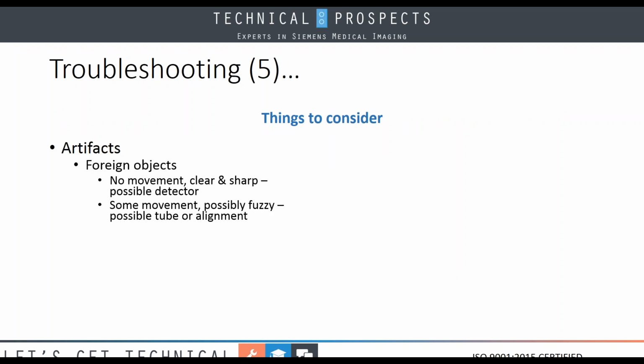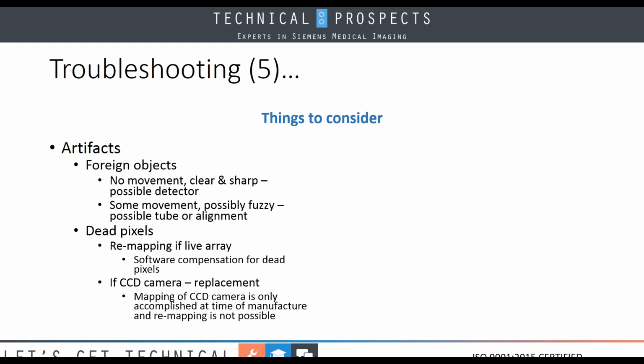When we look at artifacts here, foreign objects, all right, if they don't move and they're clear as sharp, it's possibly right on the detector. If they move around on different images, maybe a little fuzzy, maybe it's the tube or an alignment issue. When we look at dead pixel artifacts, all right, remap if it's a live array. The reason that remapping is important is because if the software knows a pixel is bad, it will then look at the 8 surrounding pixels and compensate for that known bad pixel. If it's a CCD camera, unfortunately, mapping is only done at the time of manufacture. And if pixels start going bad, the only thing you can do is replace the camera.